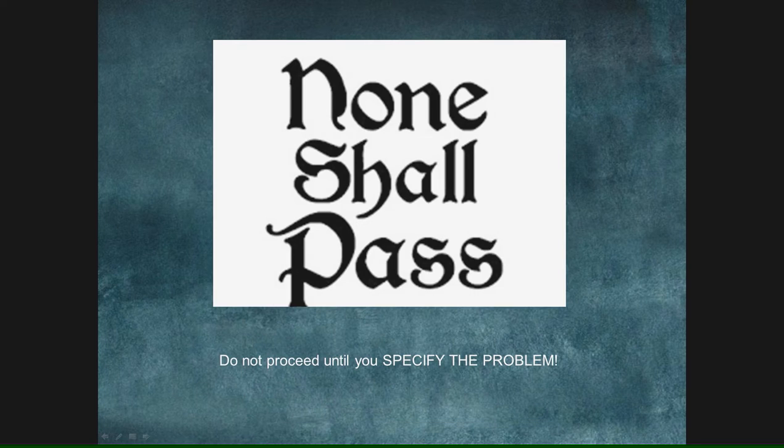I'm a bit of a Monty Python fan. "None shall pass." The first and most important step is to realize what the actual problem is. If you haven't done this, don't go through the creative problem-solving process. For example, if a nurse reports that the defib is broken, have you identified what the actual problem is? You're probably going to have to ask: how is it broken? What doesn't it do that it did yesterday? You've got to ask this question first.